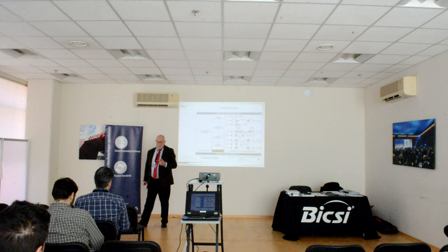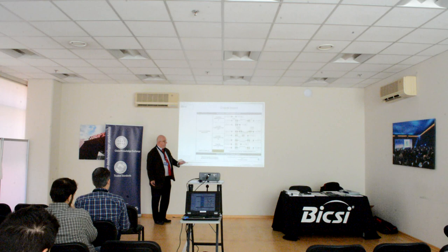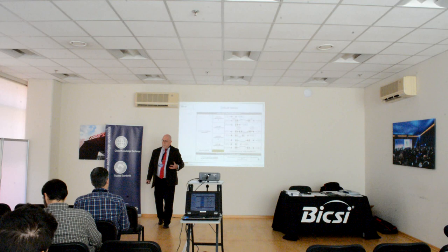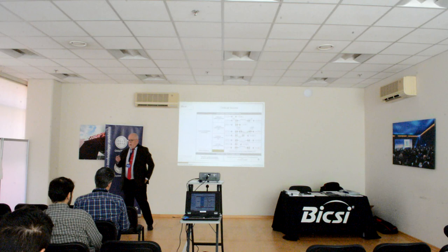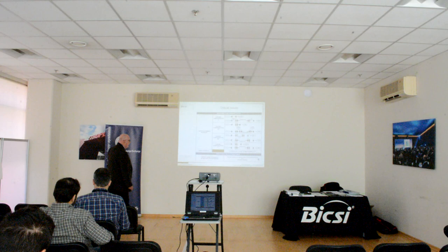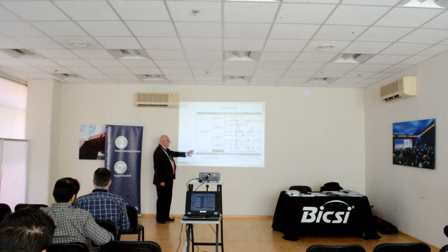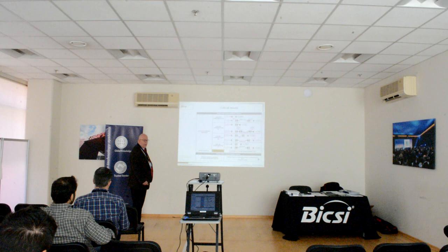But that was bad enough, and you can blame the UK for most of these things, because it's my guys in the UK that found multimode testing depended on launch conditions. So you can blame us for that, but one thing you can't blame us for, and what we now have a problem with in a lot of installations, is the term reference ports, reference grade terminations. Virtually all the standards either push you towards or mandate you use reference grade terminations on your test cords and in your test adapters.